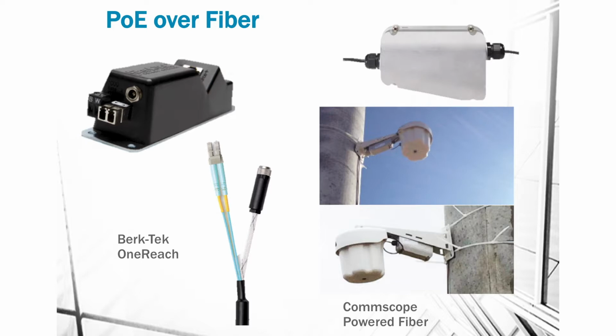Best practice, as you said, if the cabling spec requires passing test results per the TIA standard, you're going to run into complications. So the solution is to identify your camera locations ahead of time that are beyond your distance limit, and I've been advocating for PoE over fiber.